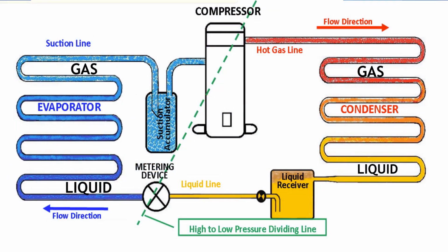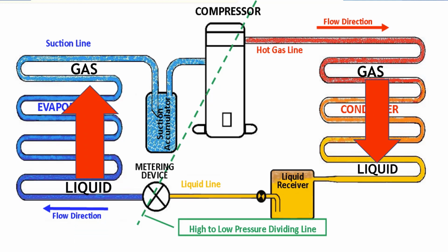The condenser is a heat exchanger used to condense a gas into a liquid state through cooling. Latent heat is released by the gas and transferred to the surrounding air. The latent heat required to boil off the refrigerant from a liquid to a gas is taken from the air as it passes through the coil, thus cooling the air. This boiling process is called evaporation. Thus, the coil in which this occurred is referred to as the evaporator.